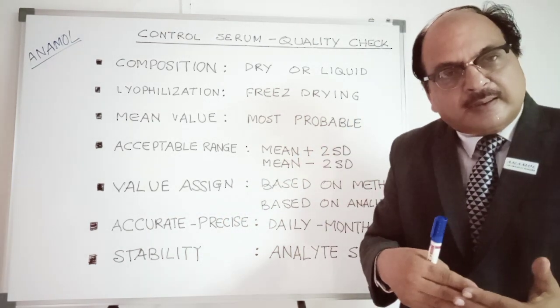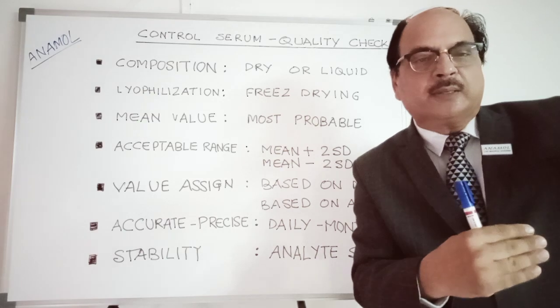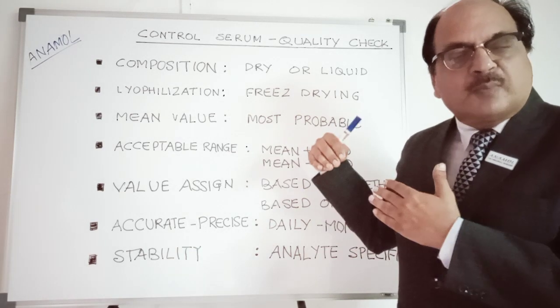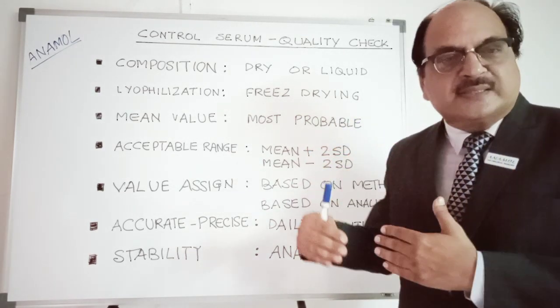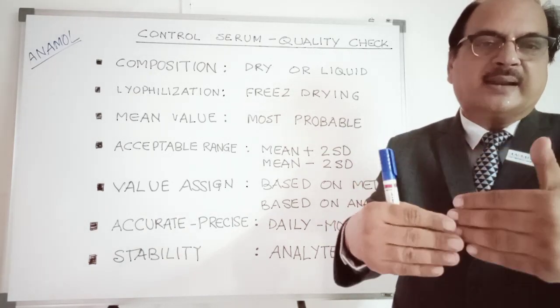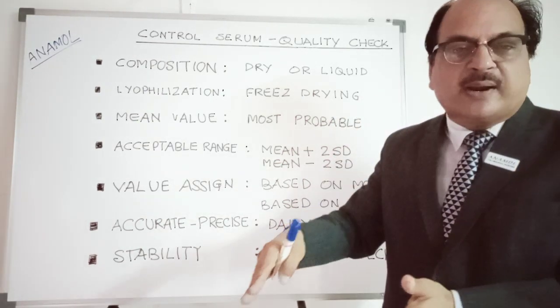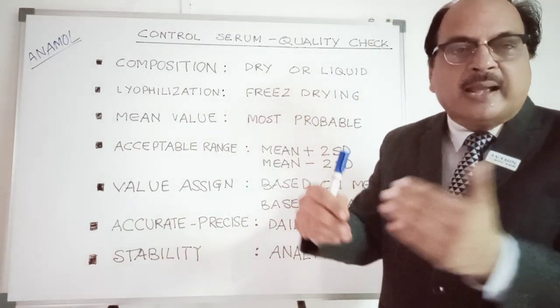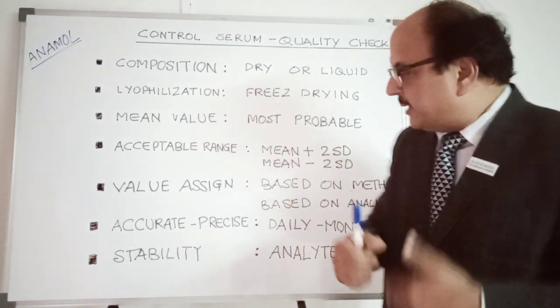Values are also assigned based on the analyzer — Beckman Coulter, Hitachi, Abbott, and others. If your analyzer is listed, you simply use the value specified for that analyzer, since it uses a specific set of reagents. If your analyzer is not in the manufacturer's list, you take the general method-based mean value and match it to your reagent methodology as per your technical insert.